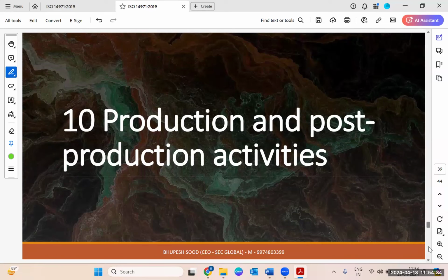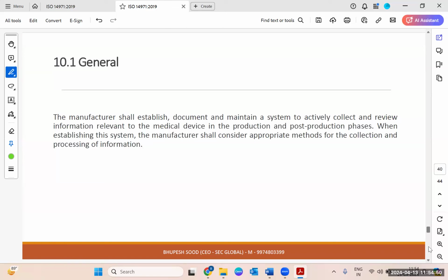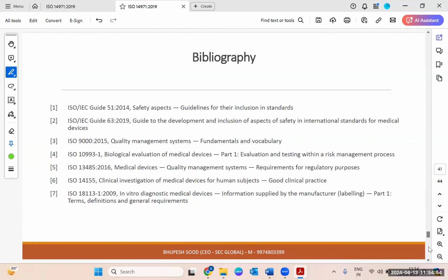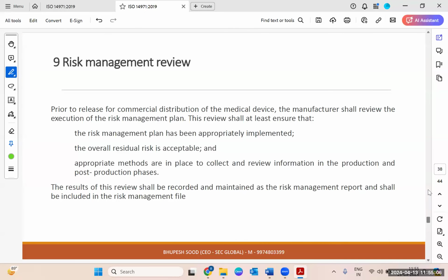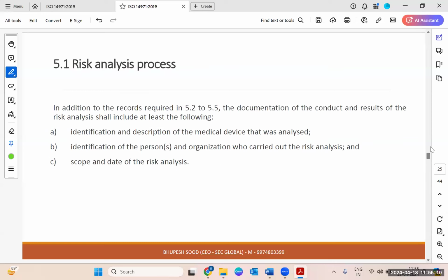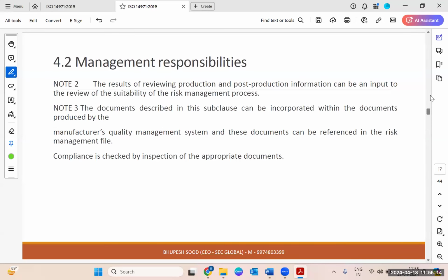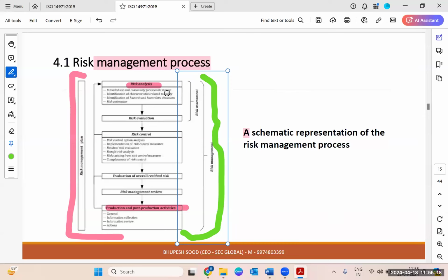Then we have the production and post-production. That means once you've released the product in the market for commercial use, you can also monitor the product and see if any update needs to be made in the risk management plan and risk management rating. So that is an overall cycle, a bird's eye view of the risk management plan across its various stages: you start the risk analysis, you evaluate it, then you control it, evaluate the overall residual risk, have a risk management review, and once that is done, you do the post-production release.